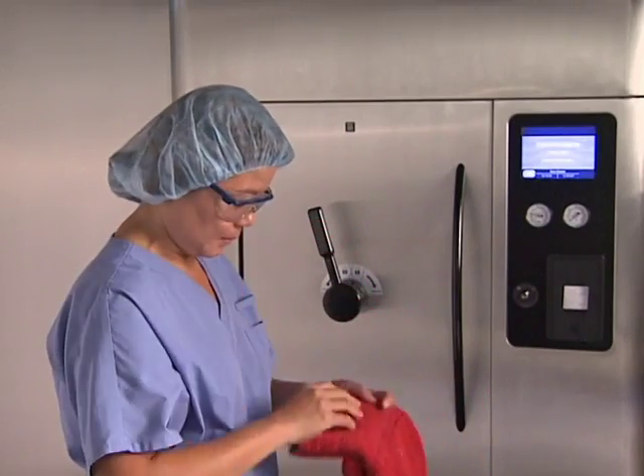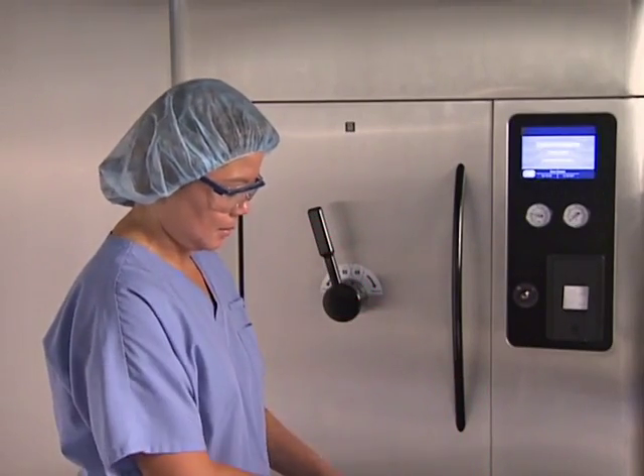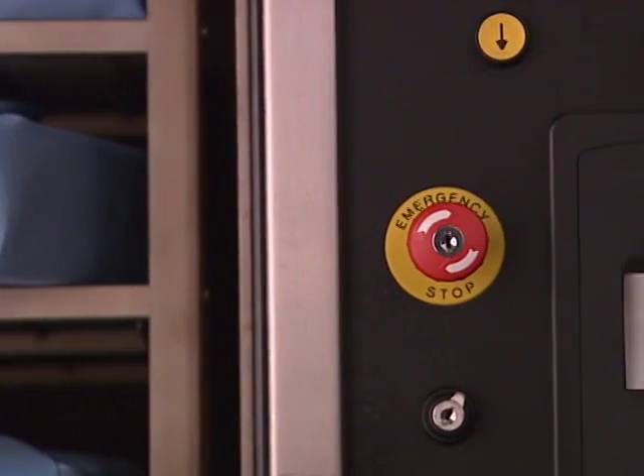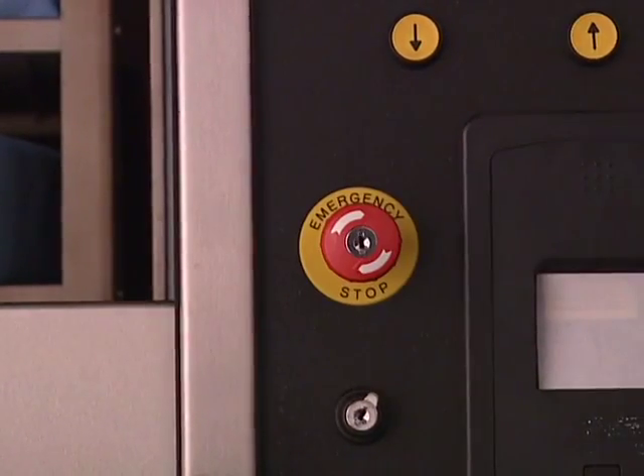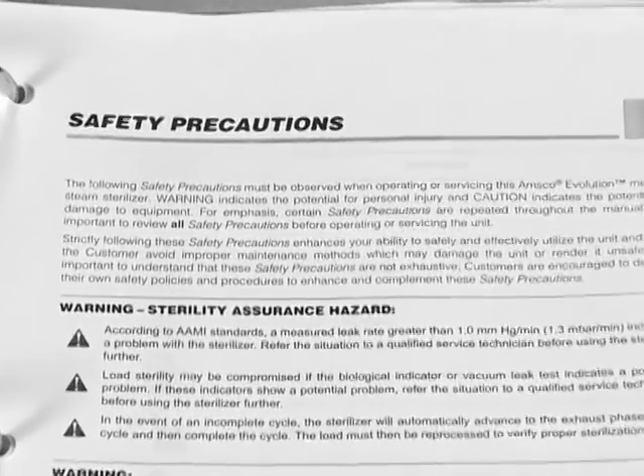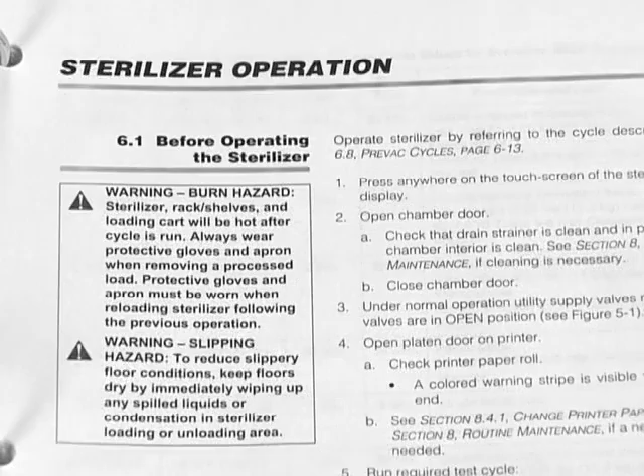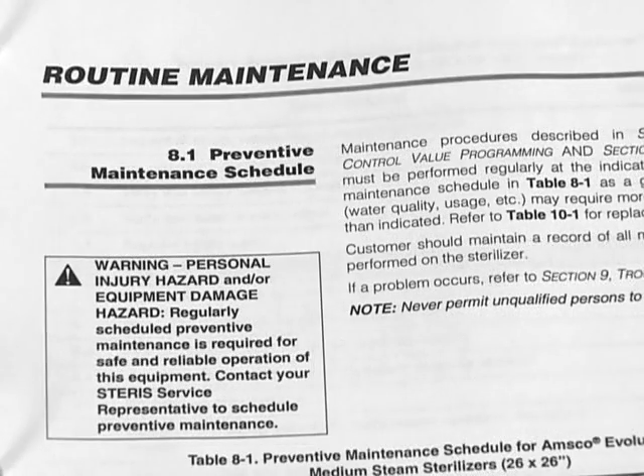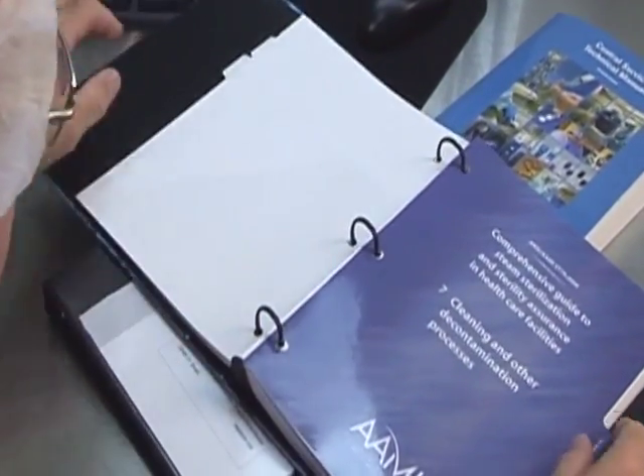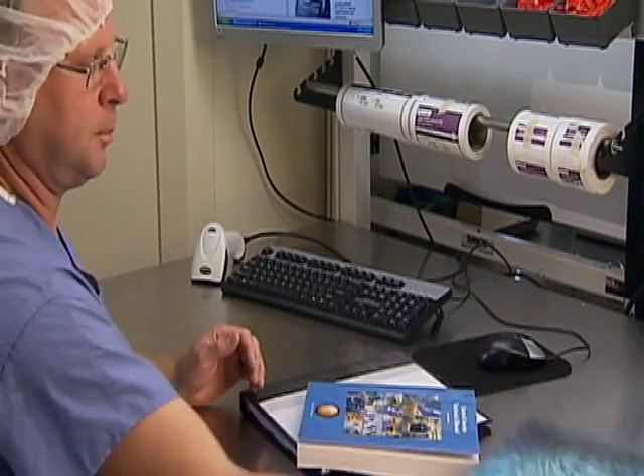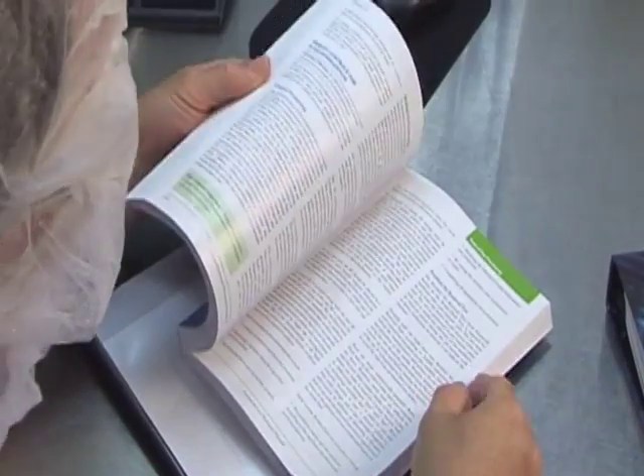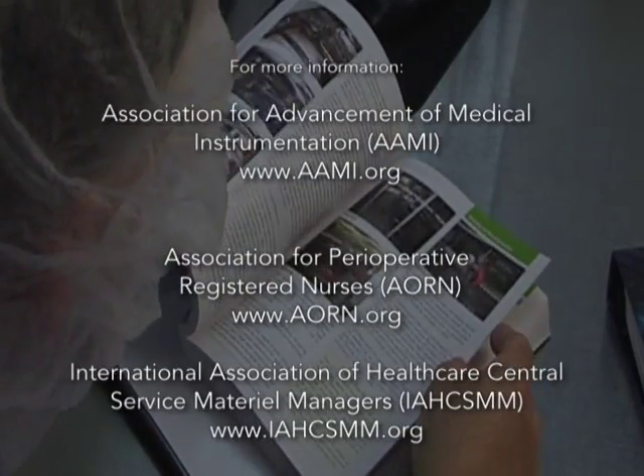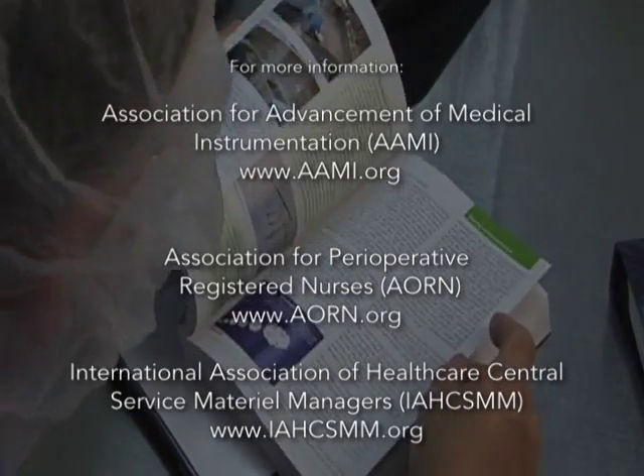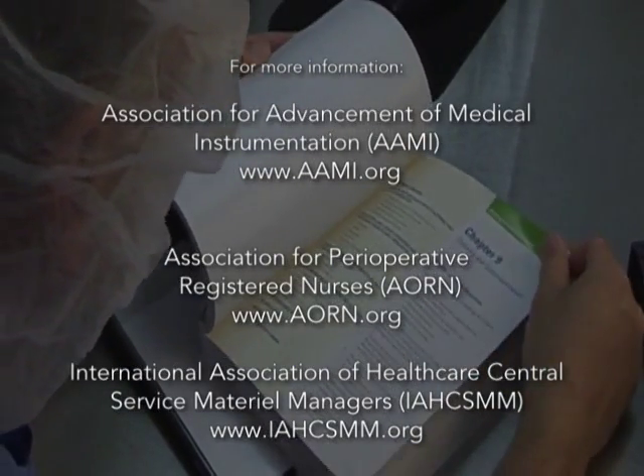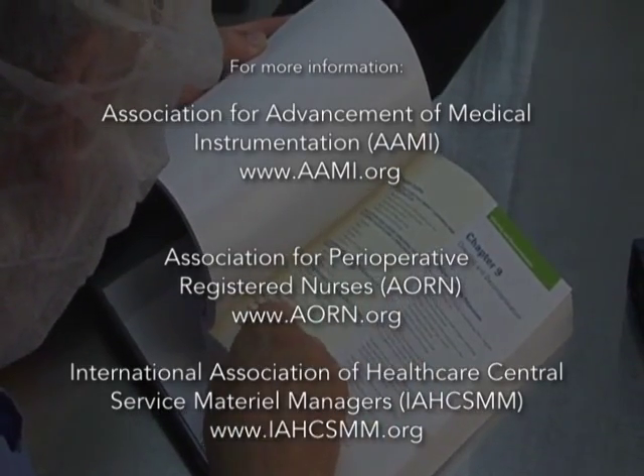Safety, yours and the patient's, is an important part of the sterilization process. The Evolution series sterilizers include a number of important safety features. Be sure to read all of the safety warnings and cautions that are detailed in the Safety Precautions, Sterilization Operation, and Routine Maintenance sections of your Evolution Sterilizer Operator Manual. For additional information on sterilization standards and practices, STERIS Corporation recommends you review the guidelines published by industry associations such as AAMI, AORN, and IAHCSMM. Following these guidelines for cleaning, packaging, and loading instruments is the first vital step for effective steam sterilization.